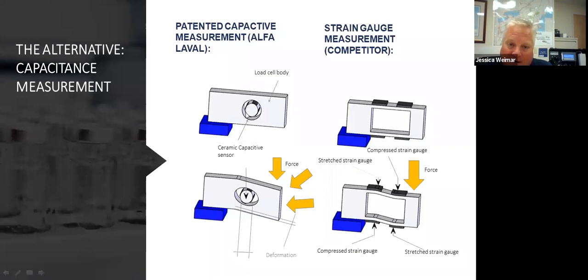So think about, you see this air gap inside of here. As the cell is deflected, these elements are capable of measuring a distance change between those two surfaces. You'll see here, as the cell is deformed, the hole becomes oblong, and those distances change, as do these distances. That cell is able to measure that distance change and then translate that into a weight measurement. This is kind of important. Think about something. On the strain gauge side, we're subjecting the sensing element to the load. In this side, we're not. The sensing element never sees the load change on the beam. The only time it would see it is if you exceed the elastic limit of the beam itself and it failed. Then it would contact the load cell sensor. So this is really important.